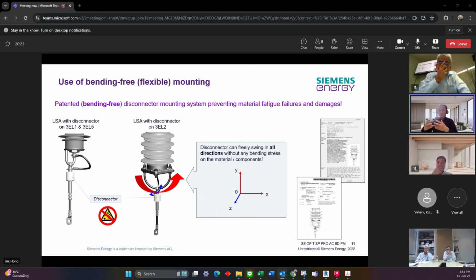So the surge arrestor itself is still okay, electrically it is still okay, but the disconnector itself will be disconnected by mechanical force. So it happened many times in different countries and different customers. From the Siemens side, we have a very special and patented design to avoid such a fatigue problem, which means we have a 3D flexible movement system for connection of the disconnector to avoid the mechanical stress or the tension on the disconnector itself.